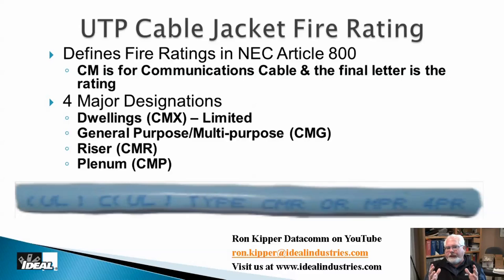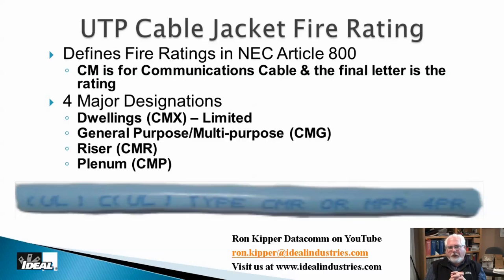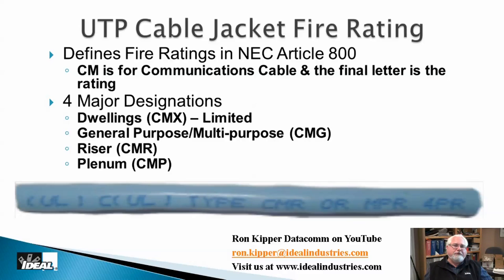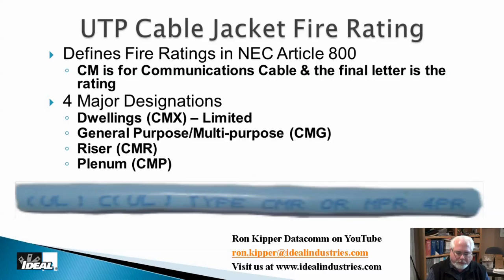Plenum-rated cable is designed for use in HVAC air plenums. In many office buildings, drop ceilings are part of the HVAC system — a blower pulls air across that ceiling space, making the entire above-ceiling area a plenum. Any cable run through such areas must be plenum-rated. Inspectors are well aware of this requirement, so it's one of the first things they'll look for on the cables.